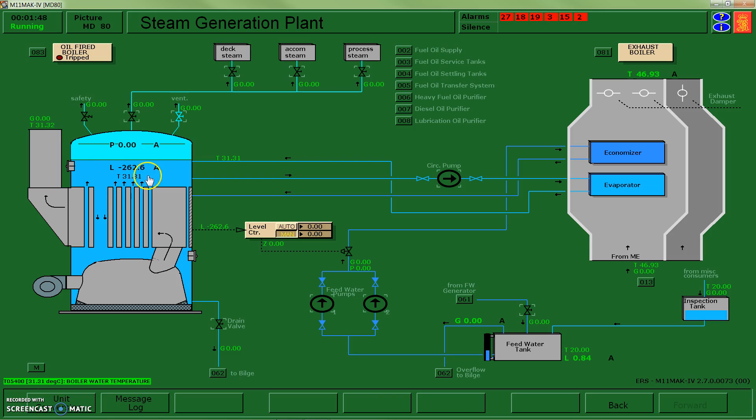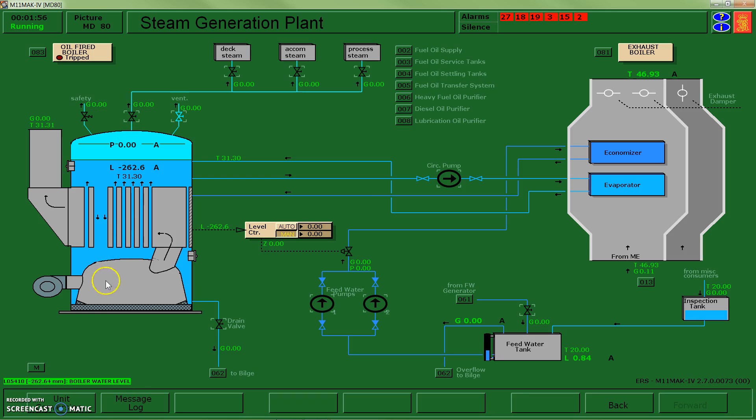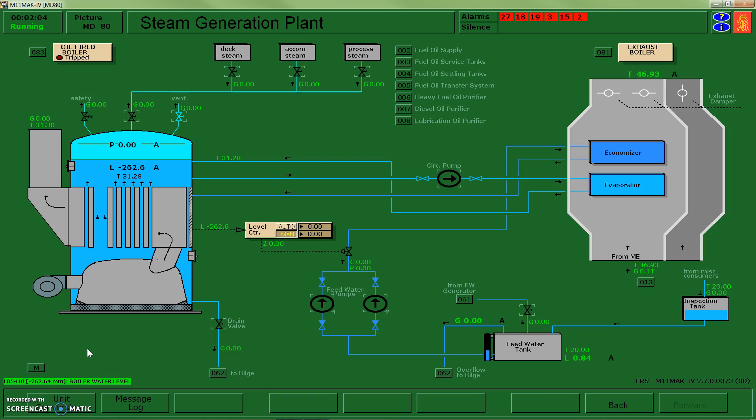If I look at my level right now, my level is at negative 262.6. What that is telling me is millimeters. You can see down at the bottom here it's millimeters. I'm 262 millimeters below my zero point or my desired point, so I could add in some more water.